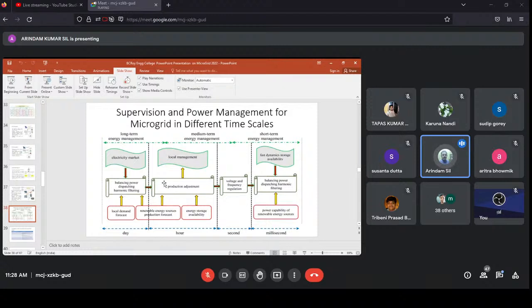After that, whatever production adjustment has been made in the local management part is fed with good quality power, taken care of by voltage and frequency regulation instantaneously by the scheduler. Then it's fed into the decision-making part in short-term energy management, handled by fast dynamic storage availability on one end, and power capability of the renewable energy sources on the other end, with balancing power and dispatching harmonic filtering done so that the entire supervision and power management of the microgrid across different time scales can be achieved.